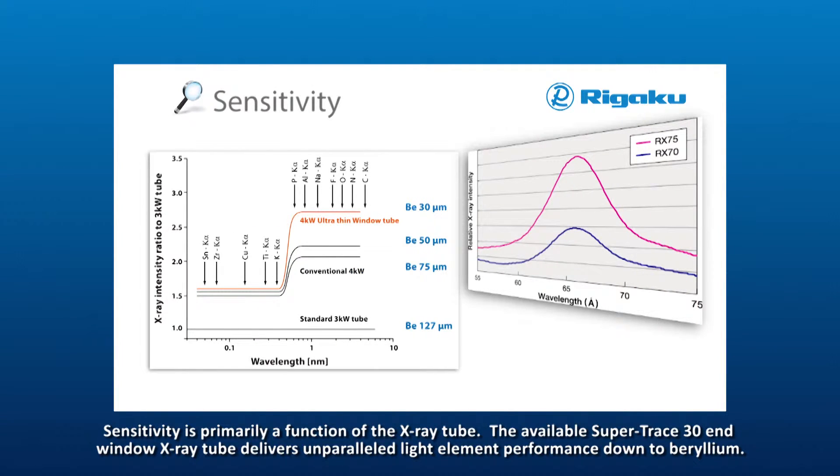Sensitivity is primarily a function of the X-ray tube. The available Super-Trace 30 end-window X-ray tube delivers unparalleled light element performance down to beryllium.